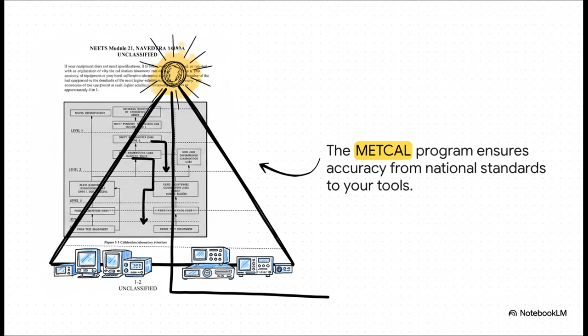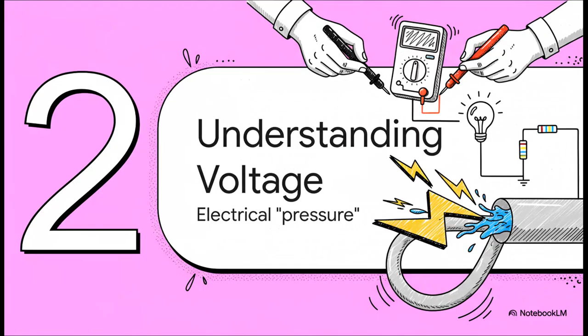This slide shows the idea perfectly. Think of it like a pyramid of accuracy. Way up at the very top, you've got the national standards, the ultimate, undisputed sources of truth for measurement. That top standard is used to calibrate the gear in the labs on the next level down, which in turn calibrate the labs below them. This creates an unbroken chain, so the multimeter in your hand way down at the bottom has its accuracy guaranteed all the way back up to that single source of truth at the top.